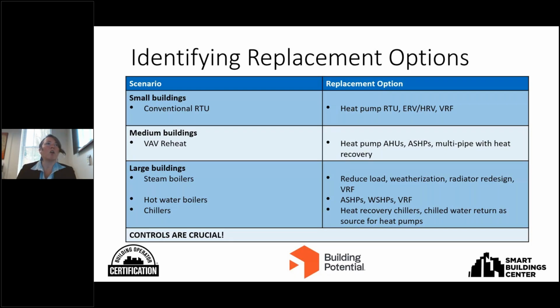With large buildings, this gets a little trickier when we get into steam and replacing steam with heat pumps. But hot water boilers and chillers, as I mentioned, certainly can be replaced with electrification technologies. Again, it's about reducing the load, weatherization, radiator redesign, and then getting heat pumps in there, as well as energy recovery.